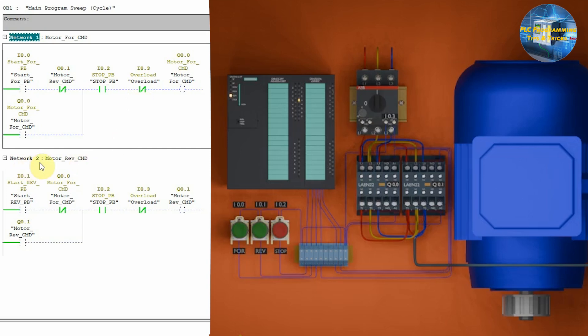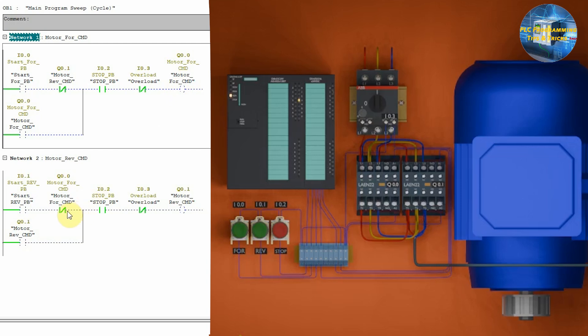In network two, we have written the logic to start the motor in the reverse direction. We have inserted a normally open contact of push button I0.1 in series with the normally closed contact of Q0.0, which is the motor forward run command.